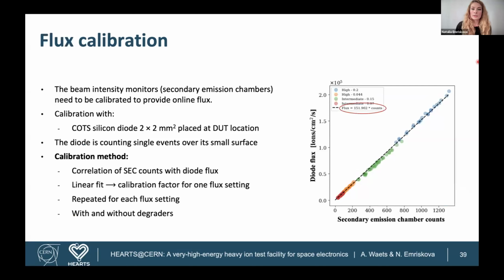So a word on the flux calibration. As I just mentioned, the two secondary emission chambers need to be calibrated such that then we can have the online measurement of the flux. We calibrate with the silicon diode, which is 2 by 2 millimeters square, and it's placed at a DUT location. So we are counting particles exactly as it is at the irradiation position. And the calibration method consists in making a correlation between the counts from the secondary emission chamber with the flux measured by the diode.